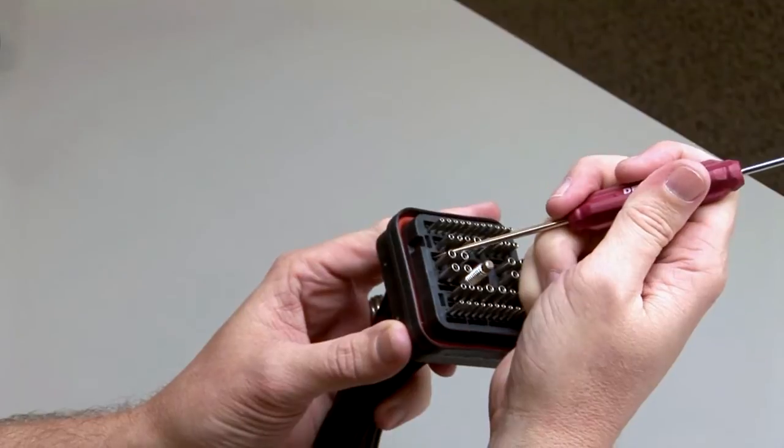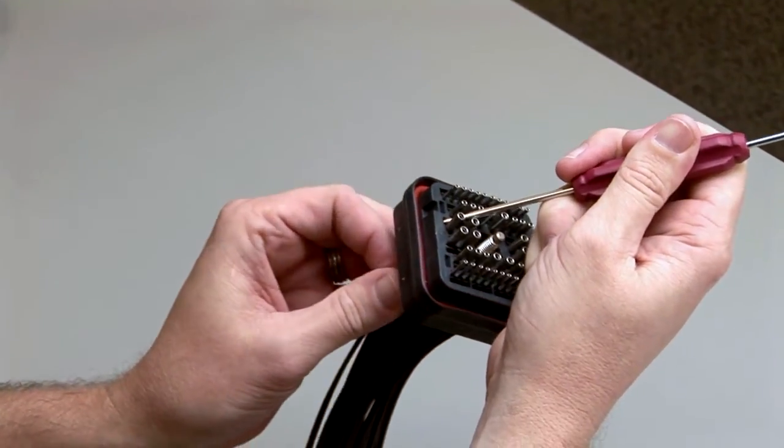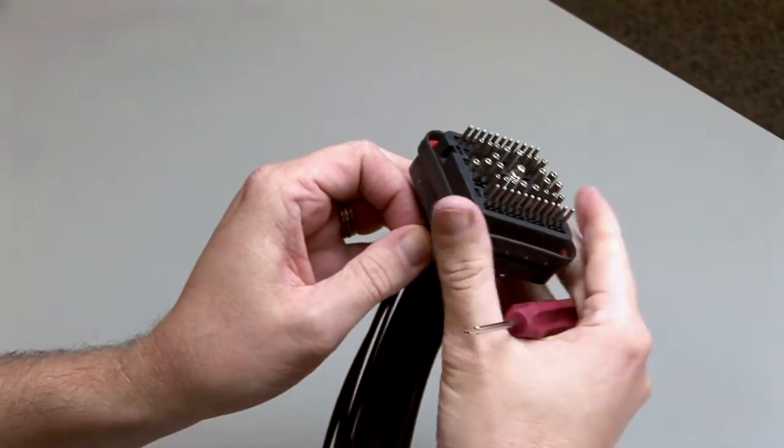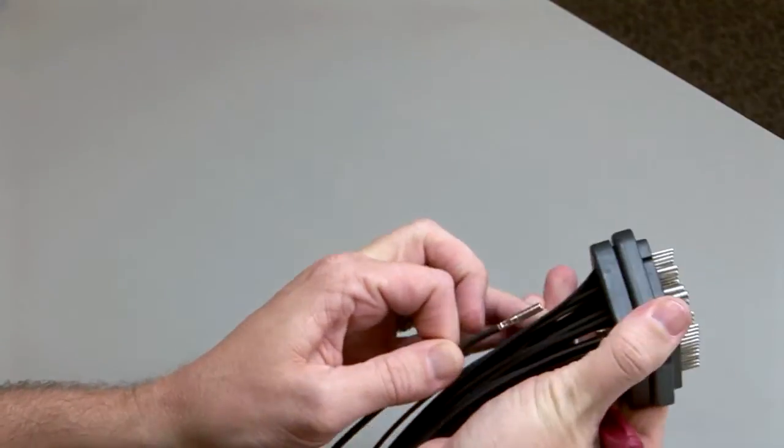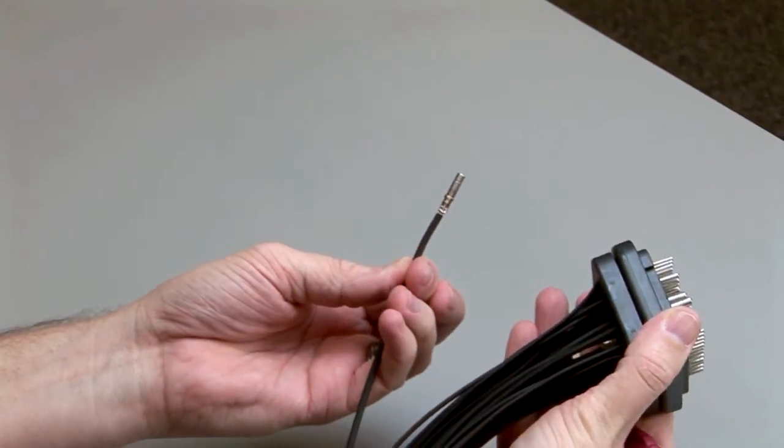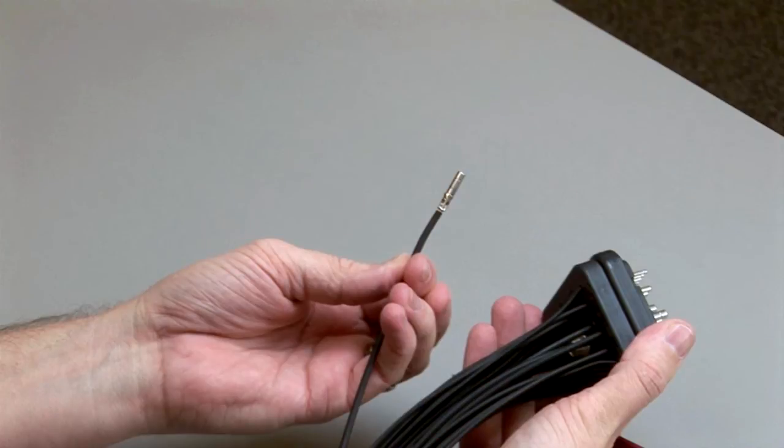To remove the contacts, release the locking finger by moving it away from the shoulder of the contact with a screwdriver, while at the same time gently pulling the wire through the rear grommet or wire router.